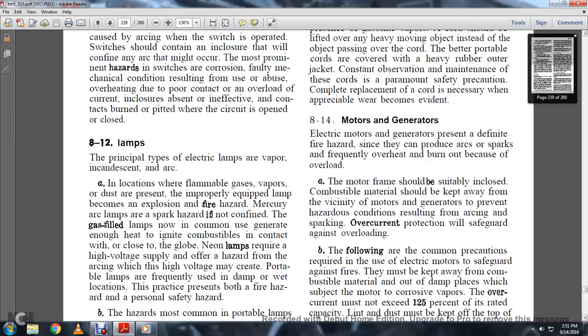8-14. Motors and generators. Electrical motors and generators present definite fire hazards since they produce arcs and sparks and frequently overheat or burn out because of overload. The motor and frame should be suitably enclosed, and combustible material should be kept away from the vicinity of the motor generators to prevent hazardous conditions resulting from arcing and sparking. Overcurrent protection will safeguard against overloading.